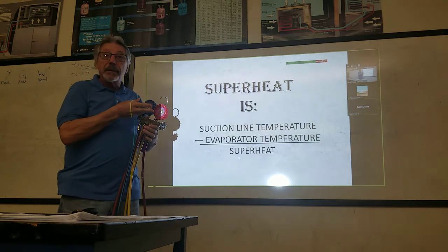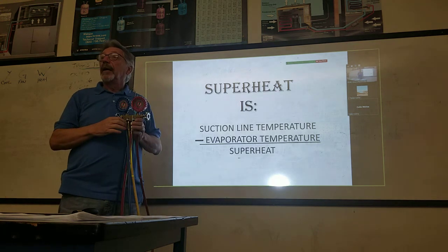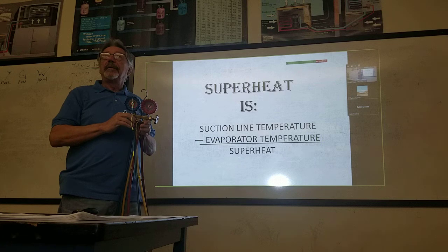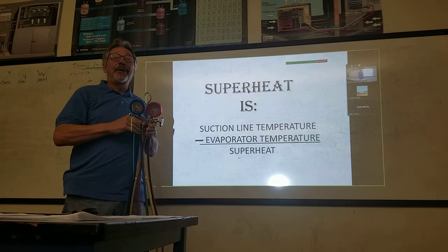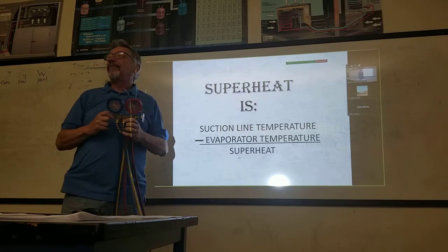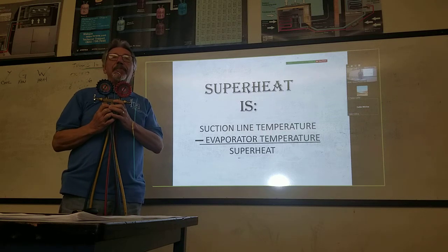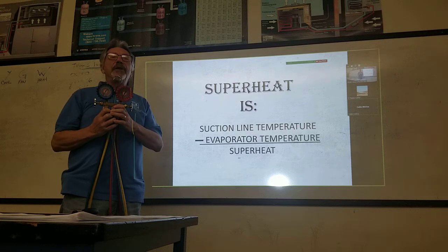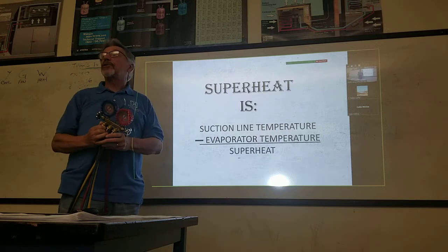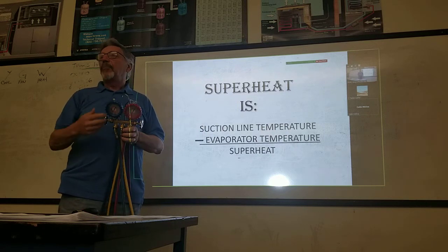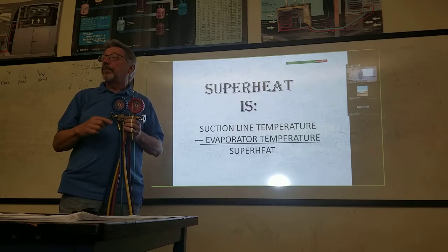The pressures that we're gonna read on these gauges, I really don't care. I don't care what the pressures are. Why do I carry them? Because what do I need from the pressures? The temperature. These are all for getting a temperature. That's all we do in our trade. We are temperature engineers. We're not pressure engineers. Whatever the pressures are, what I'm looking for is the temperature.